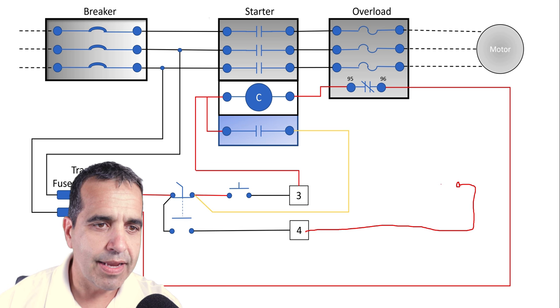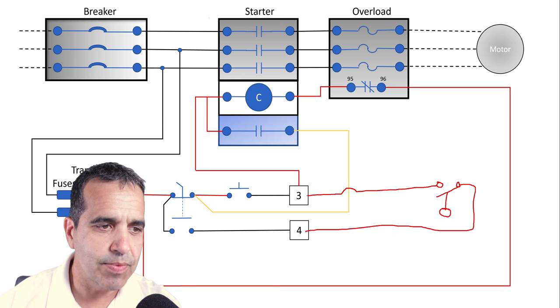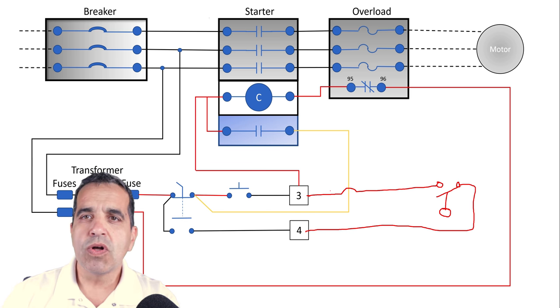We would connect it to, say, a float switch. Imagine this is a float switch, a close-on-rise float switch. Here's our float—when the water rises, the float closes. We attach another wire, come back, and jump over to number three. When that float closes, our pump would run.